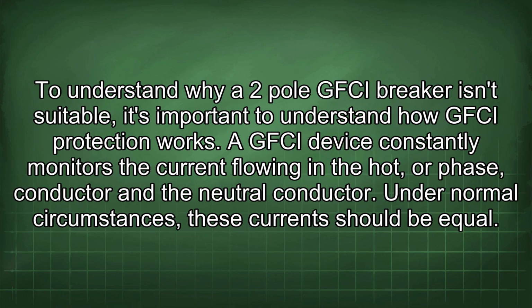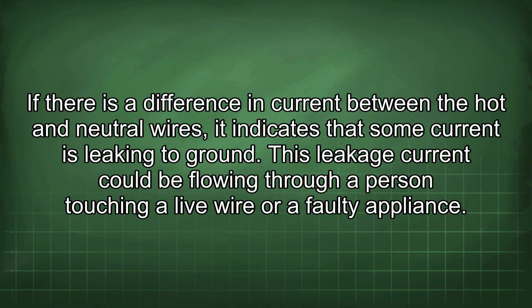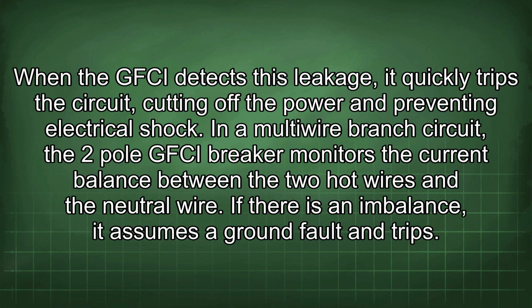To understand why a 2-pole GFCI breaker isn't suitable, it's important to understand how GFCI protection works. A GFCI device constantly monitors the current flowing in the hot, or phase, conductor and the neutral conductor. Under normal circumstances, these currents should be equal. If there is a difference in current between the hot and neutral wires, it indicates that some current is leaking to ground. This leakage current could be flowing through a person touching a live wire or a faulty appliance. When the GFCI detects this leakage, it quickly trips the circuit, cutting off the power and preventing electrical shock.